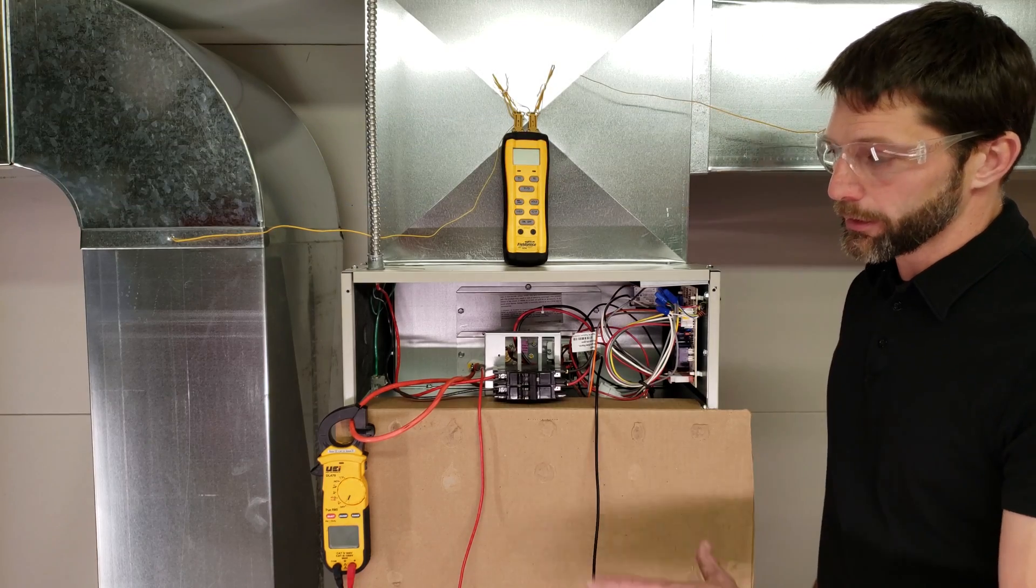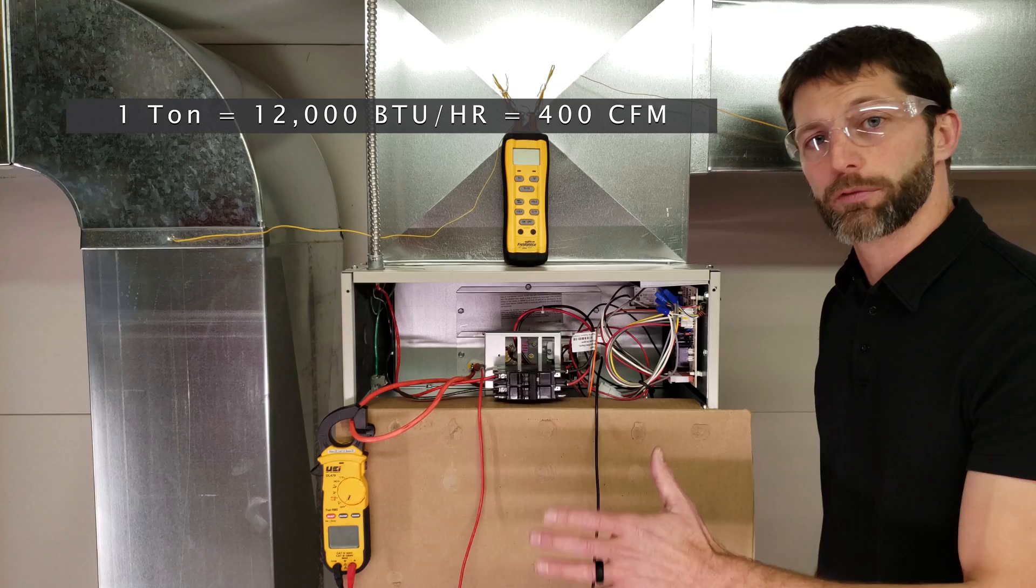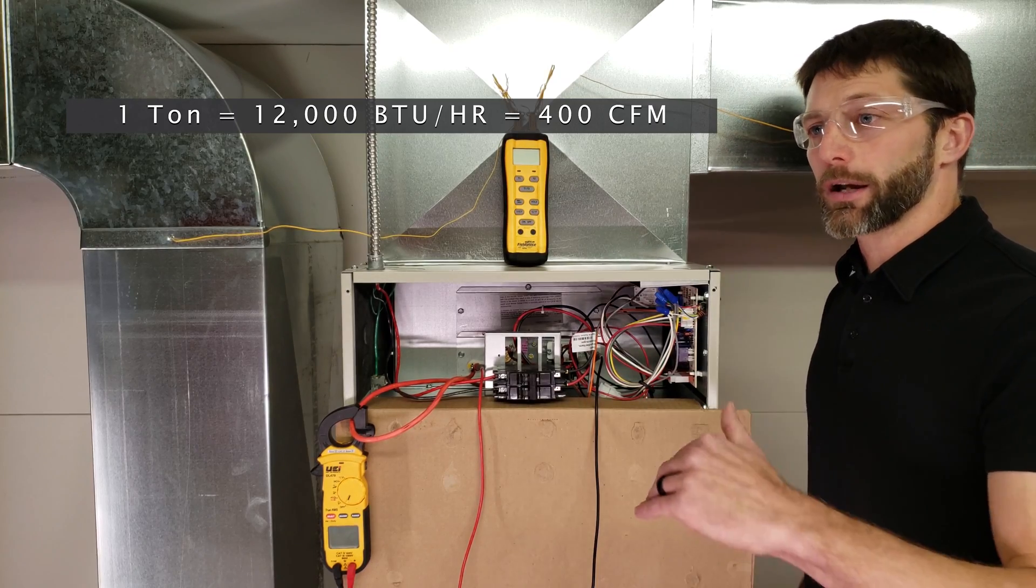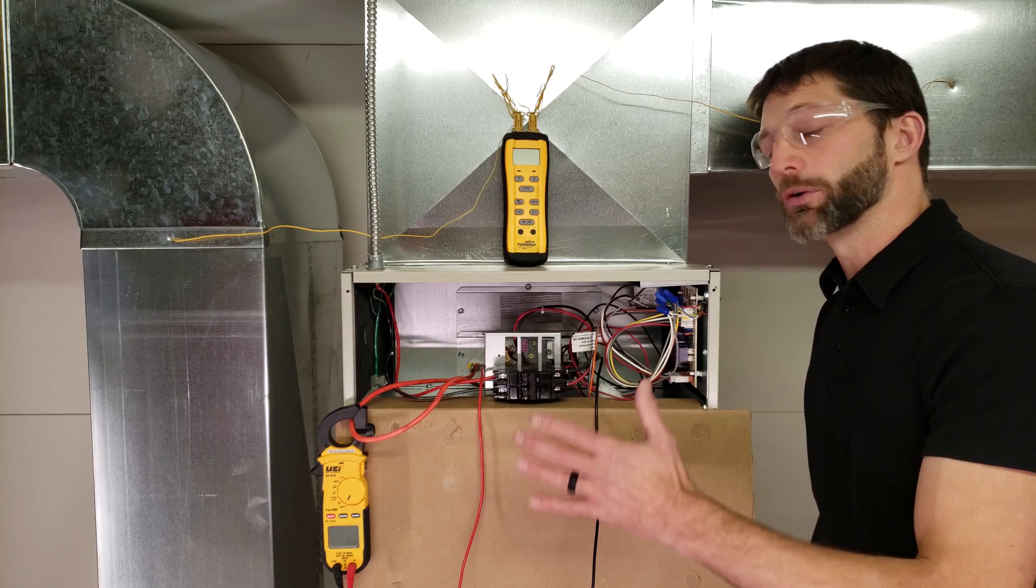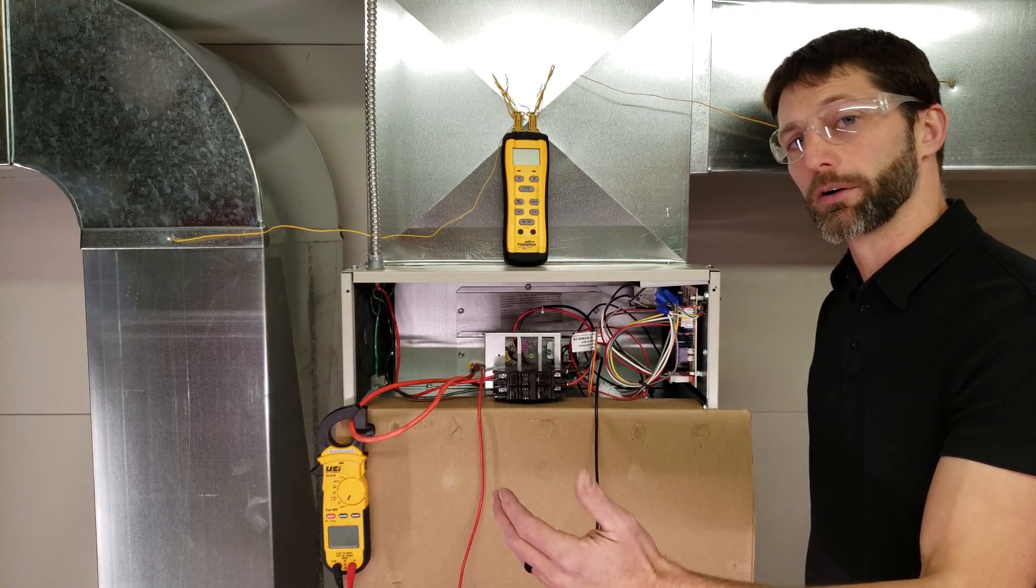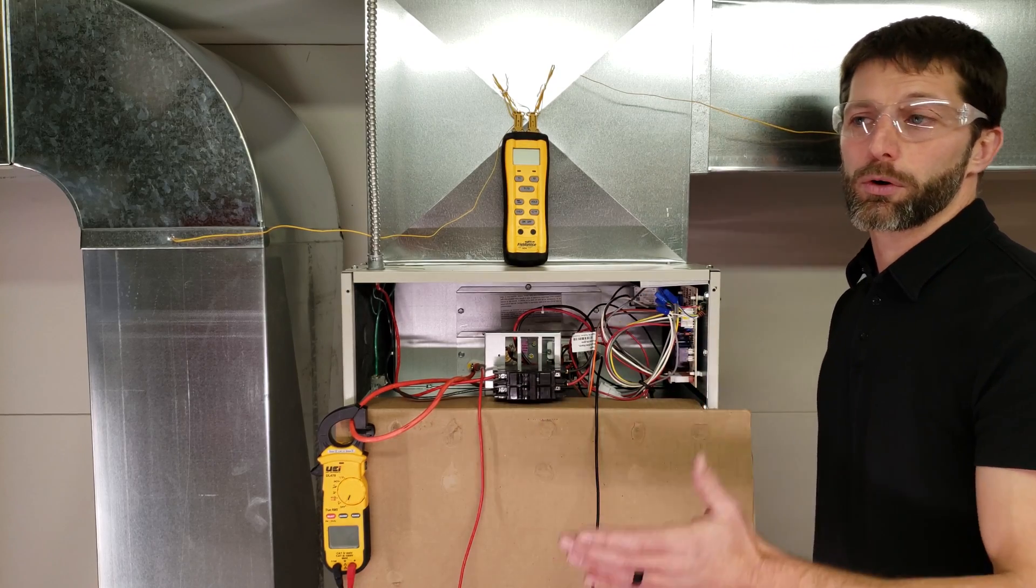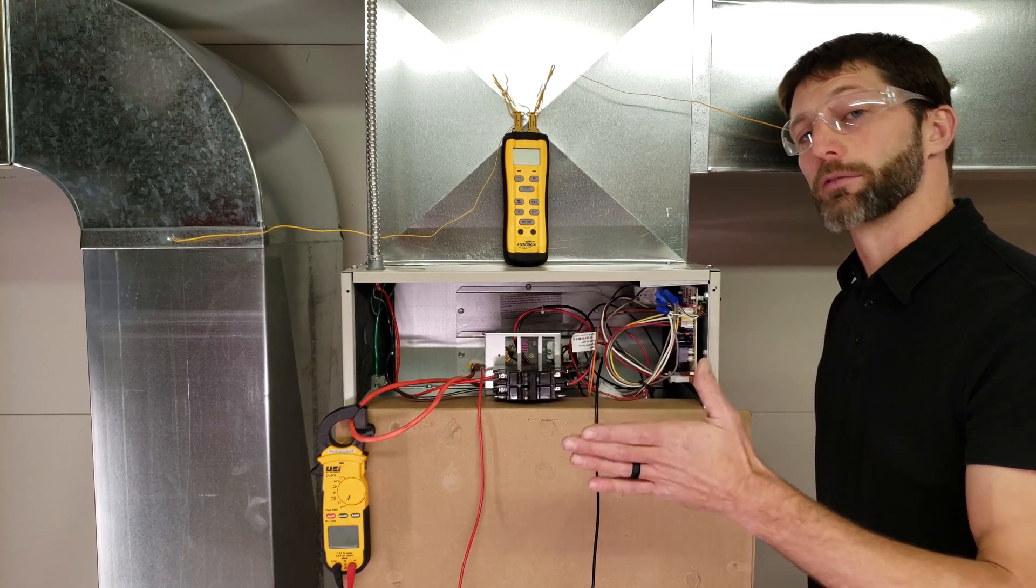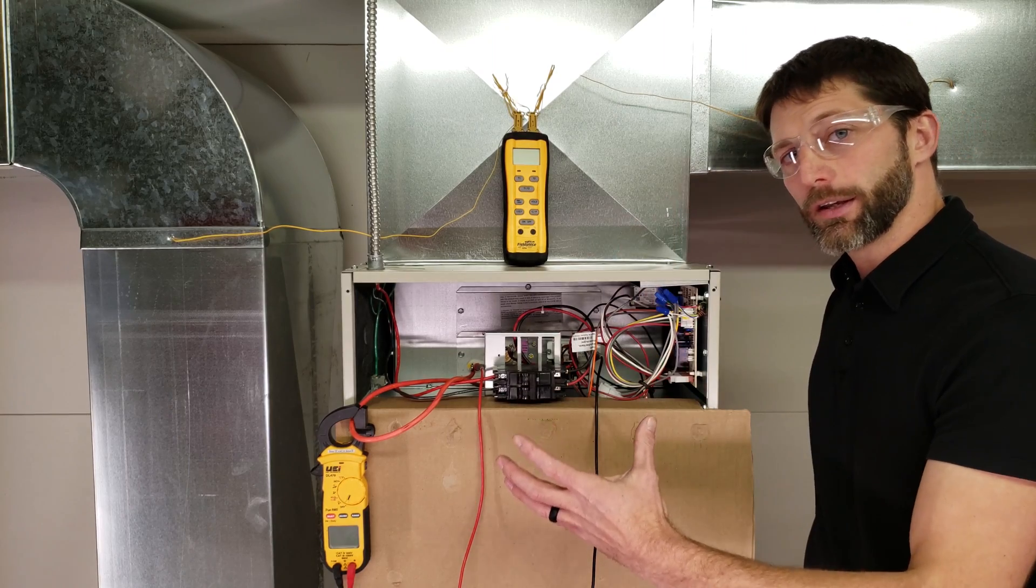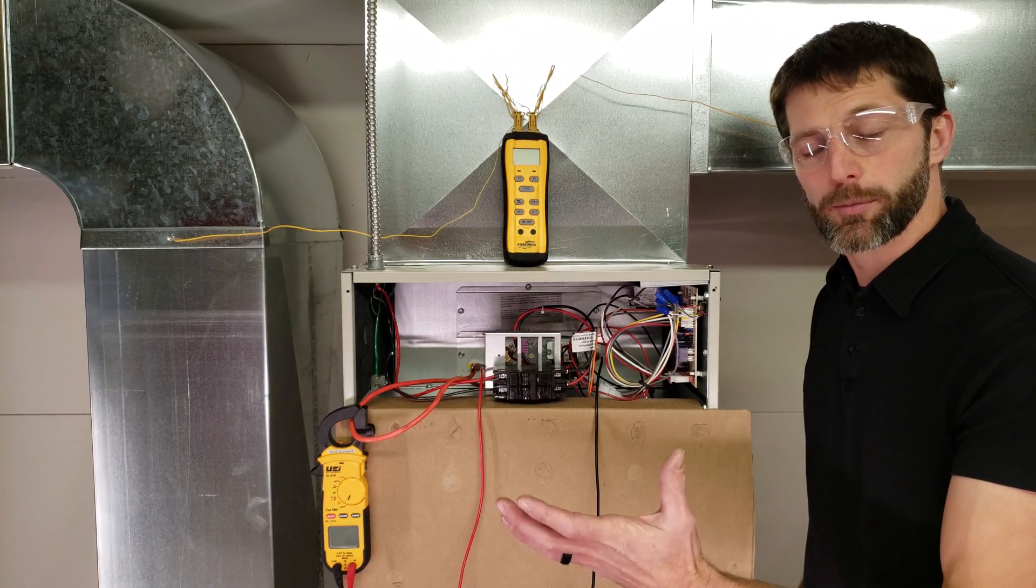So what you want to remember is that for every ton of capacity, you want about 400 CFMs of airflow for a cooling system, for an air conditioning system. So that could be, say, 350 to 425 CFMs. And you could have on the lower side that 350 if you're trying to remove a lot of humidity out of the building. But we're right about on the higher side right there. We're at 430 CFMs per ton. So 860 CFMs divided by two for a two-ton capacity equals 430 CFMs.